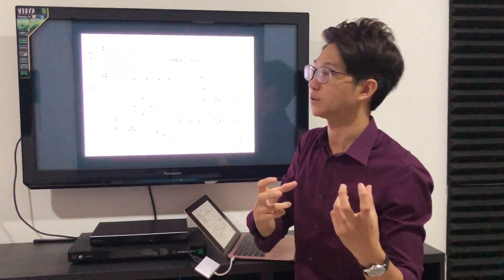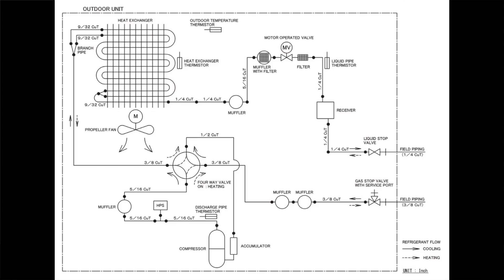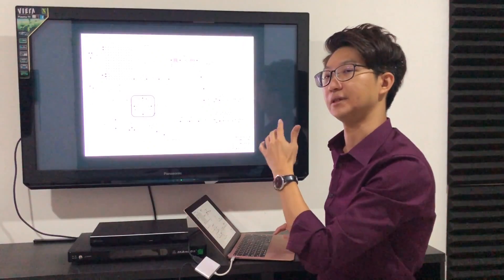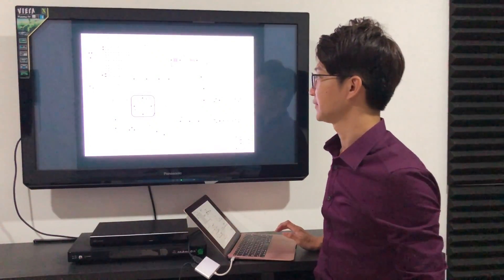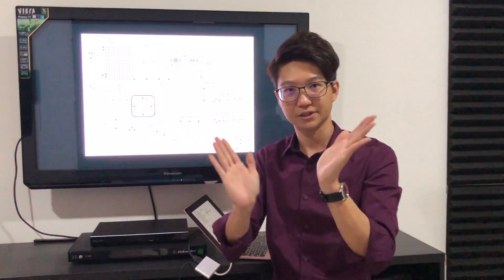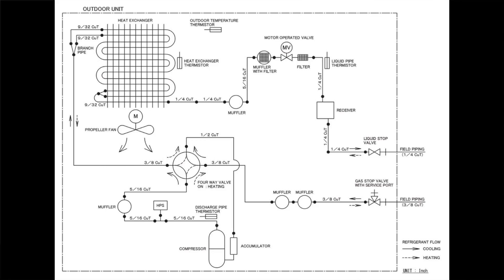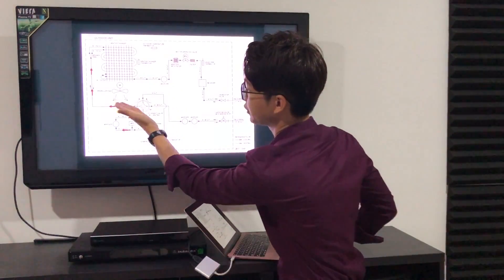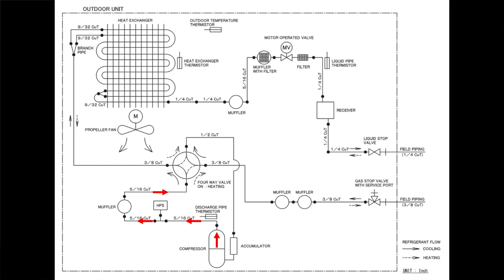The schematic shows the compressor, heat exchanger, and expansion valve. For a heat pump, there is an extra four-way valve — also called a reversing valve — which diverts the refrigerant in different directions. In normal cooling mode, refrigerant starts from the compressor as hot gas and goes to the four-way valve, which is set to cooling mode. The refrigerant then flows to the outdoor heat exchanger first, which acts as the condenser, condensing the hot gas back to liquid.